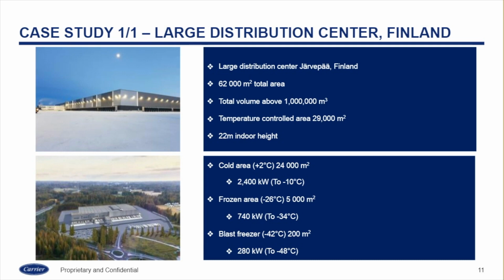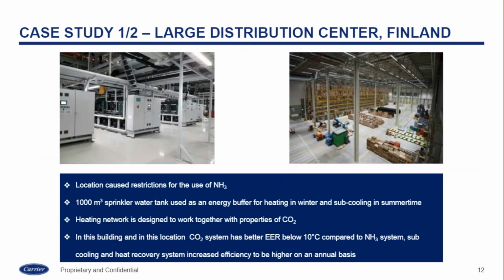Next page, please. This is some of the technology we are using. First, in this area ammonia is constrained from use. Meanwhile, we are using a sprinkler water tank as an energy buffer to store energy for heating in the winter and for subcooling in the summertime. Also, considering the heat recovery system, we designed the heat network within the CO2 product to gain the biggest benefit from the system. And considering the system EER, below 10 degrees the CO2 actually has a much more significant benefit compared to the ammonia system. Okay, next page, please.